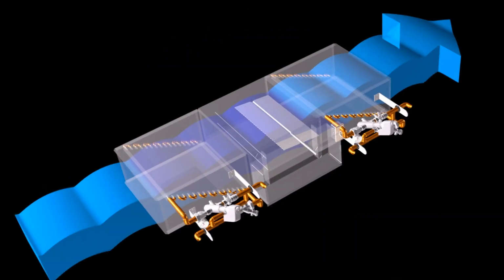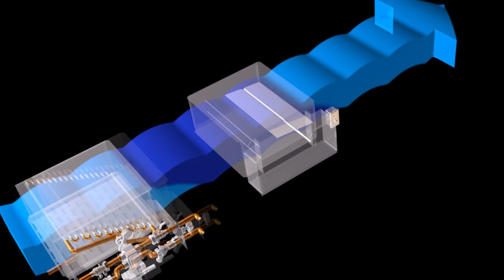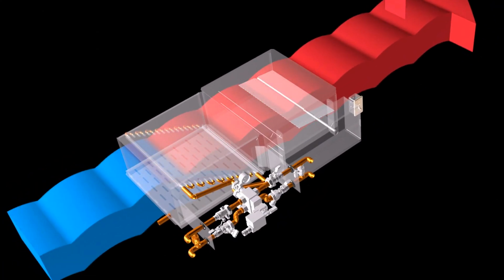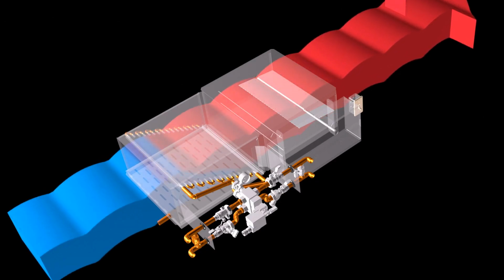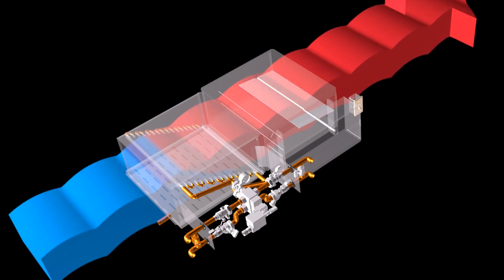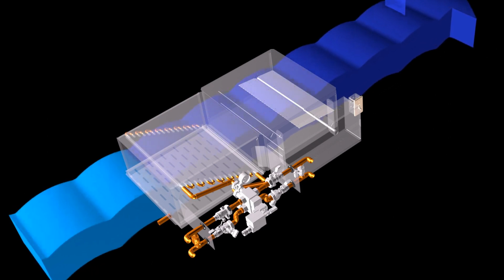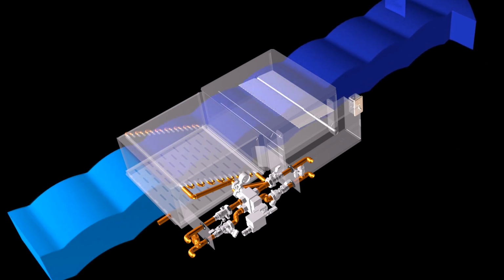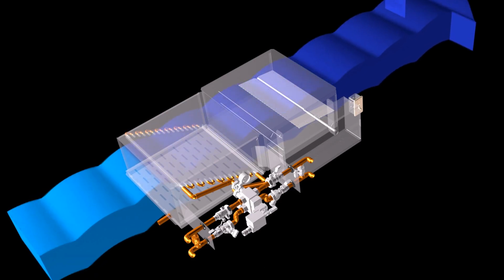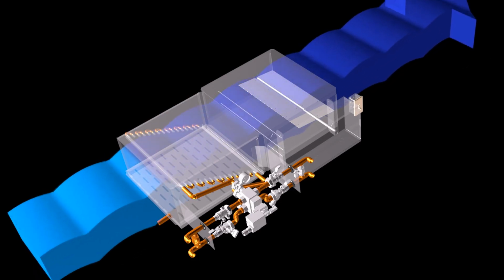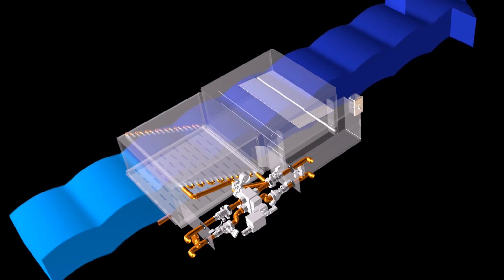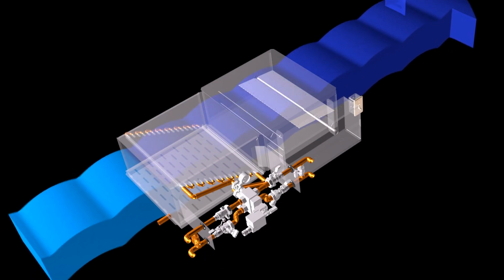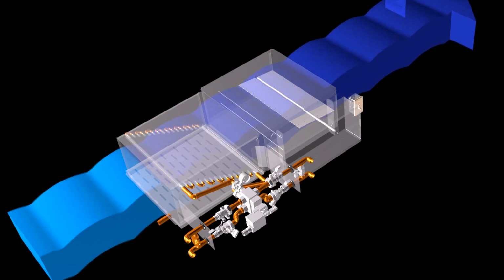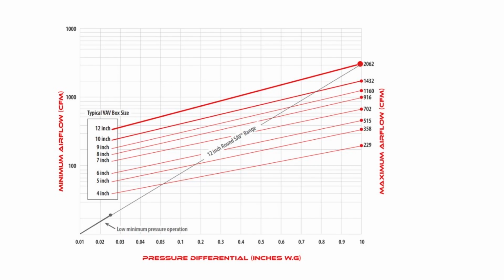A single-size SAV unit has similar performance as multiple calibrated fixed orifice air terminals and has a range of 2,500 feet per minute to 25 feet per minute with airflow accuracies to within a few CFM and accurate to 0.03 inches of water gauge. The SAV mitigates overcooling and heating of zones and operates as a pressure compensation damper proportional to airflow and temperature set points. A single-size 12-inch SAV has the same range as multiple 4-inch to 12-inch conventional air terminals.